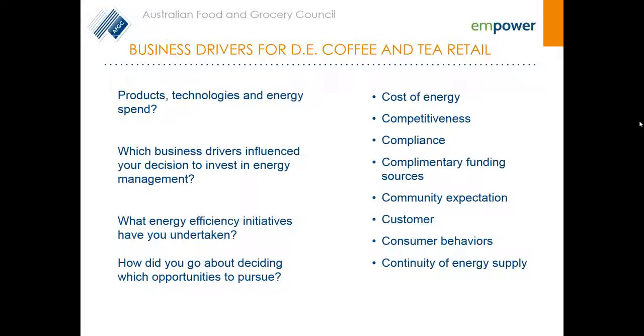One of them, which was quite simple to do, really, was power factor correction, because we were running at about 0.7, and although that technically doesn't change a lot with regards to your emissions and the like, it saved us a lot of money. So it saved us about $4,000 a year at the time, just to get that fixed so that we were running at the correct power factor correction.